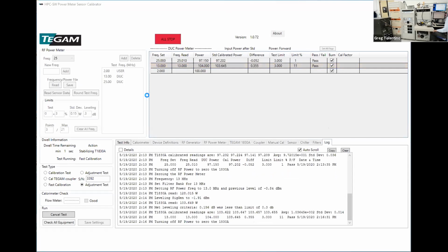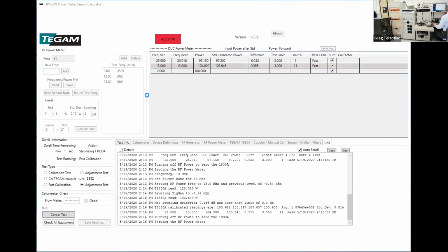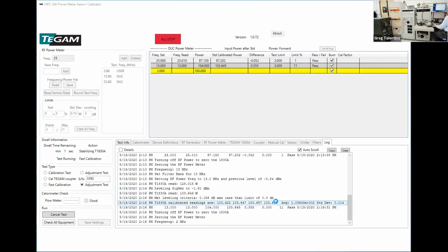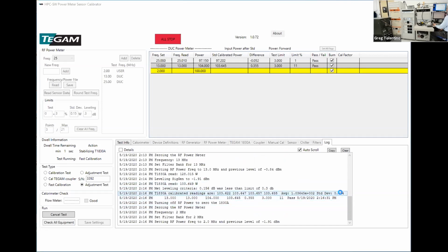So what's happening here is, let's look at this line really quick. Right before it sent the average power measurement to the Bird power meter to make the calibration, it took these 4 points, computed their standard deviation, and compared that with a criteria that I'd set in this window. That's essentially to make sure that the system is leveled well enough that it's appropriate to use that average.